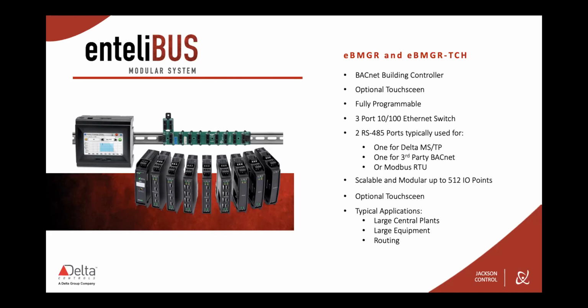It supports BACnet IP and BACnet Ethernet. There are two RS-485 ports, so one can be used for Delta MSTP, one might be used for third-party BACnet, and it also supports Modbus RTU.